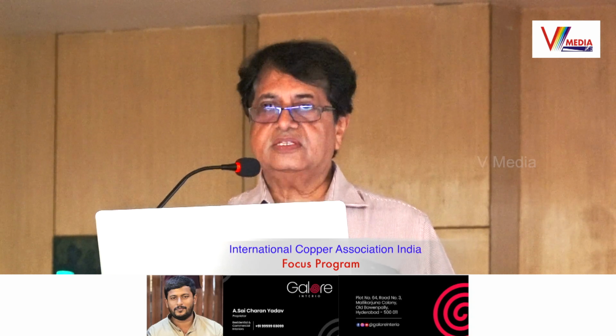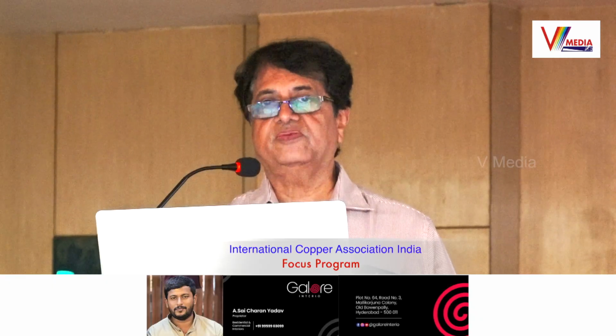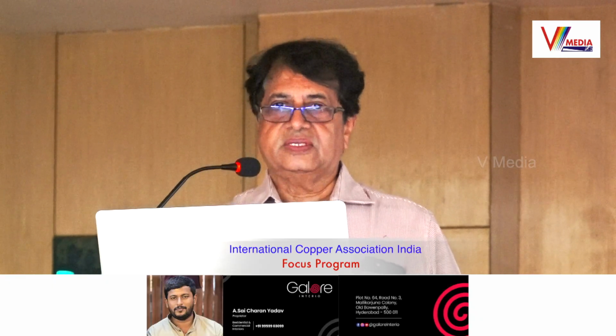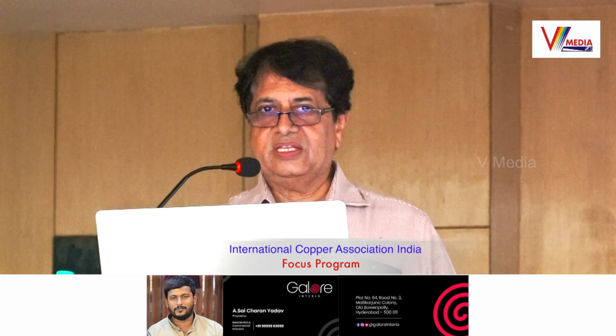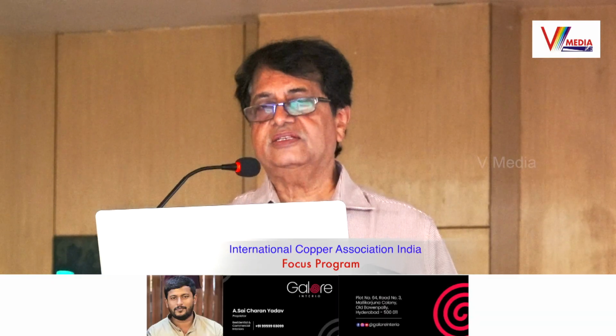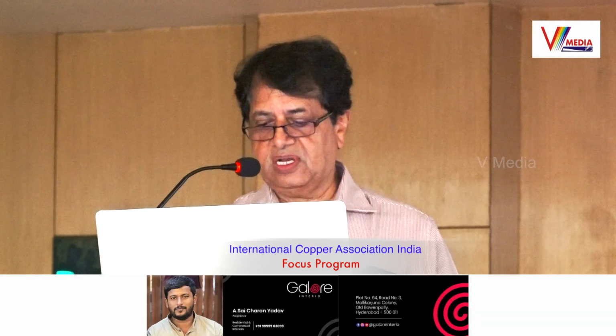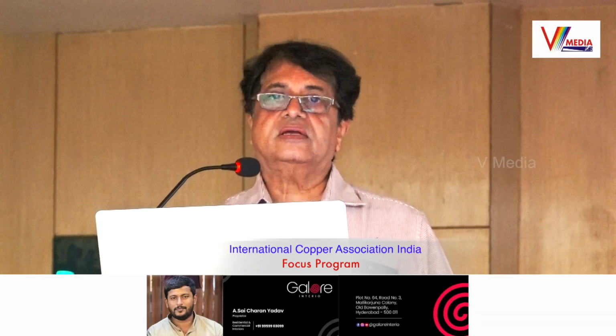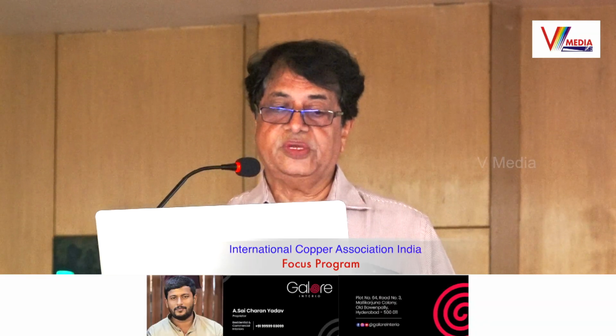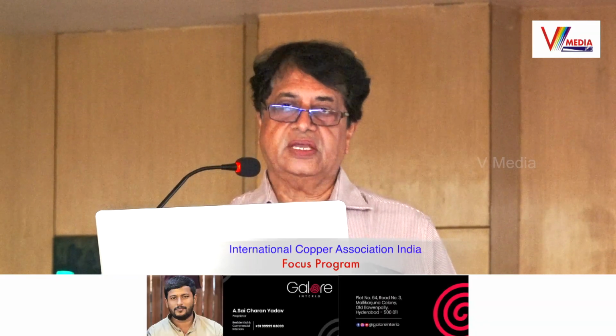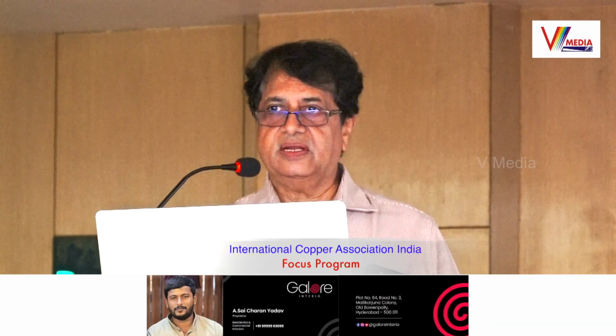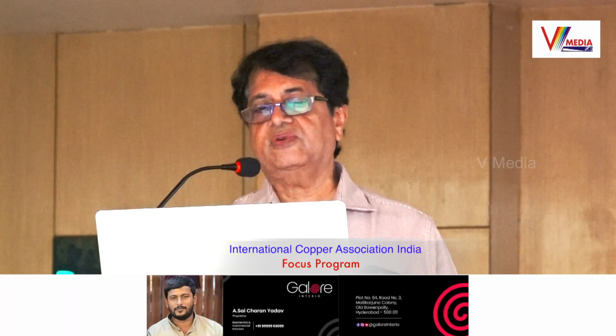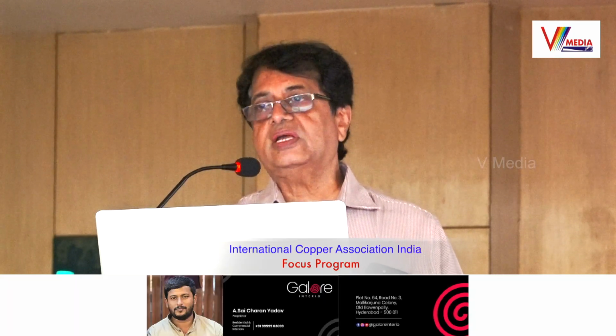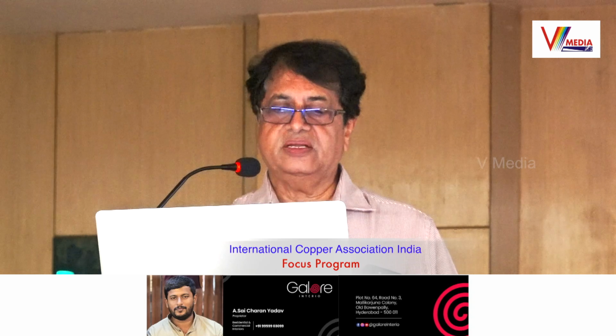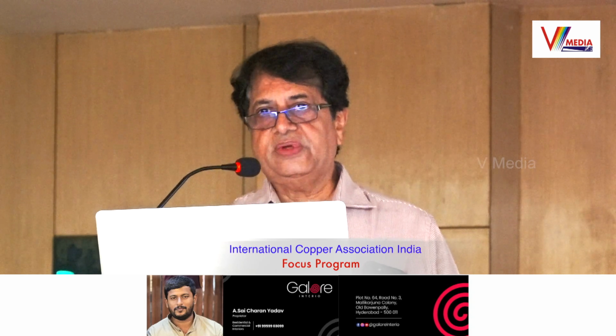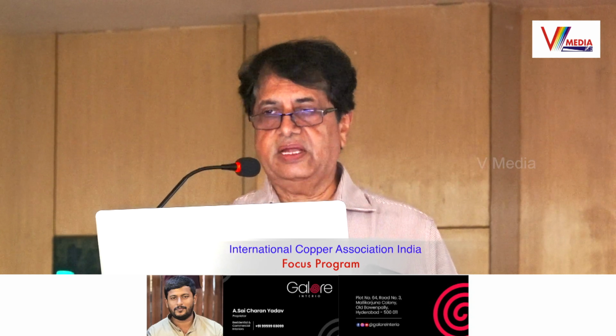Leakage and short circuit is the end result which we face, and we lose lives. See, water leakages will not cause any person to lose his life, but electrical leakages may. So here the architect's perspective comes into the picture. See, this is the faulty design. In the faulty design, there are certain requirements which are expected from the architects. If those are not taken care of at the very basic planning stage, it becomes very difficult to clear all these defects at the end.